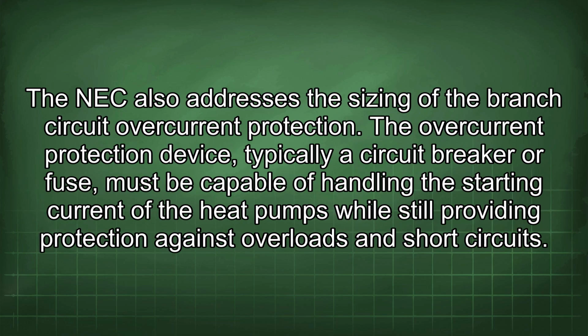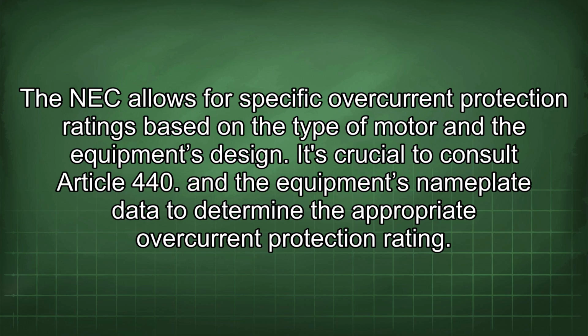The NEC also addresses the sizing of the branch circuit overcurrent protection. The overcurrent protection device, typically a circuit breaker or fuse, must be capable of handling the starting current of the heat pumps while still providing protection against overloads and short circuits. The NEC allows for specific overcurrent protection ratings based on the type of motor and the equipment's design. It's crucial to consult Article 440 and the equipment's nameplate data to determine the appropriate overcurrent protection rating.